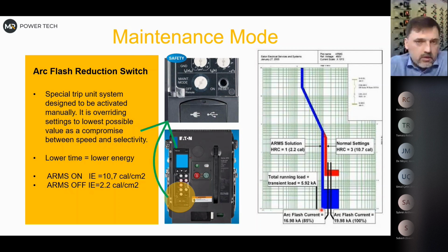And we don't change them manually. The way it works is we just activate it on or off, and we don't change any settings on the trip unit. That's the idea behind it. We then normally take it as a separate scenario in the arc flash calculations, and you might print a separate label for this kind of operation mode as a warning on your switchgear. I hope this explained the topic, but it is a bit more complicated to show, so it's better to show it on specific examples.